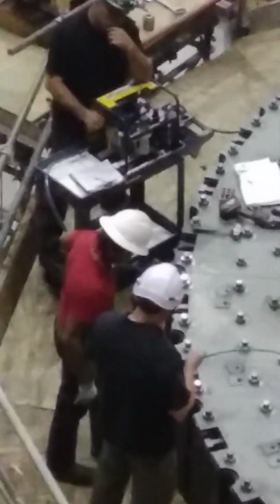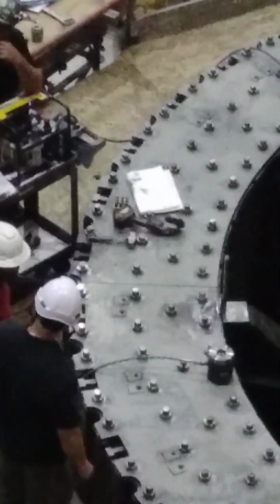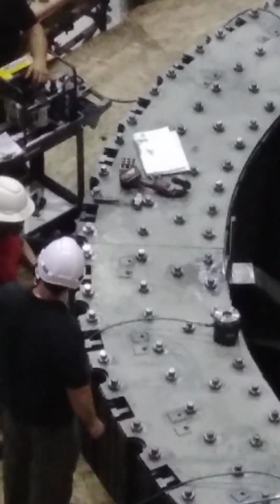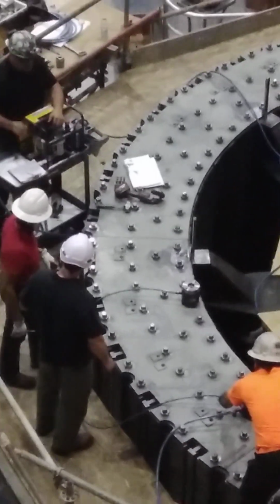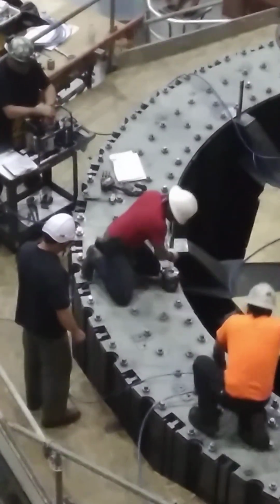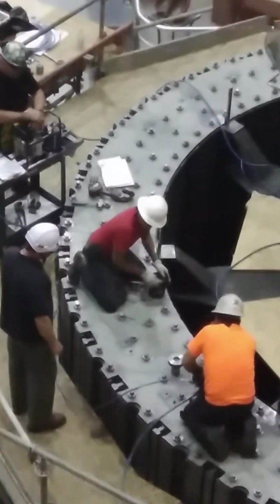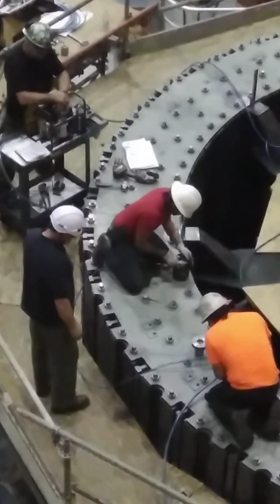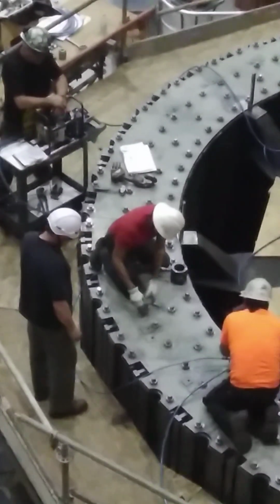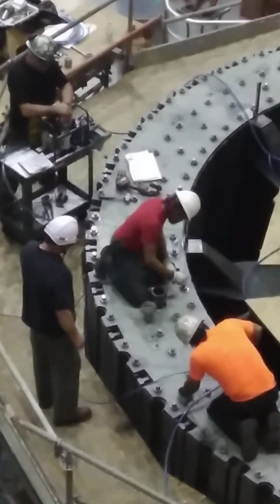Now, you are probably wondering what is going on with the rotor we're servicing here. Well, earlier I compared the generators to cars. You might also compare a generator to a guitar. You've got, when it's on, the rotor in the middle there vibrating, humming at a certain tune like a guitar string vibrates to play a certain note. The way that we know that something is wrong with one of these rotors is if it's out of tune. And well, that's exactly what was happening with this rotor right here.